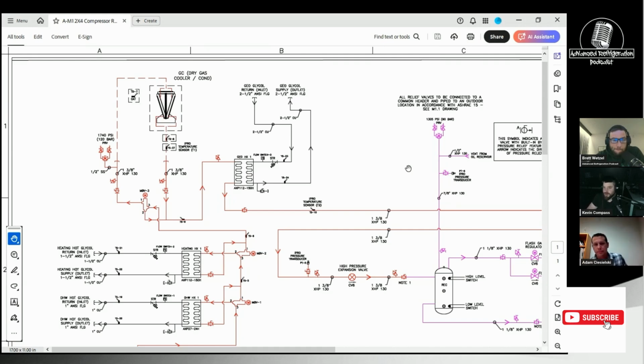And what are your thoughts on hot gas defrost? Typical supermarket system, it's slow. You don't have a lot of temperature difference to work with. So it's challenging to move stuff, because let me frame that in terms of the setup. Whether you take it off the low side of the system or the medium temp side, I prefer taking it off the medium temp side and dropping the pressure, because then you can do hot gas with the medium temp and low temp circuits. It doesn't matter.